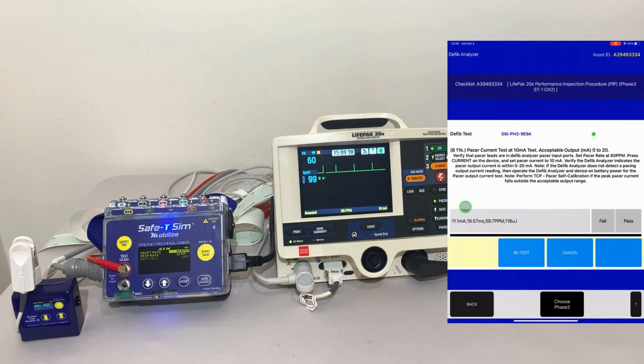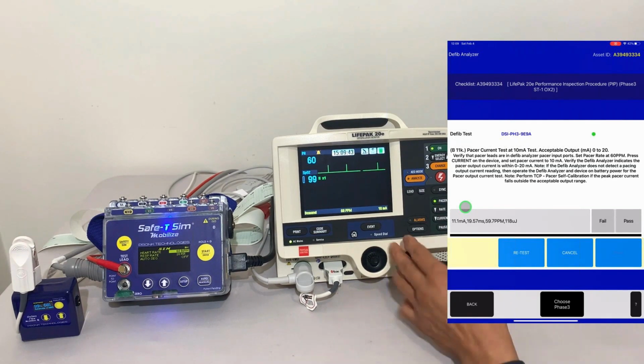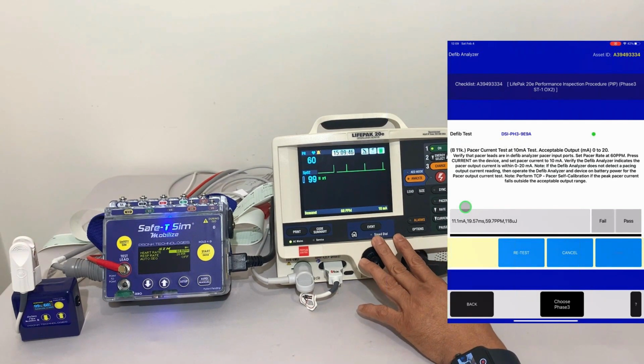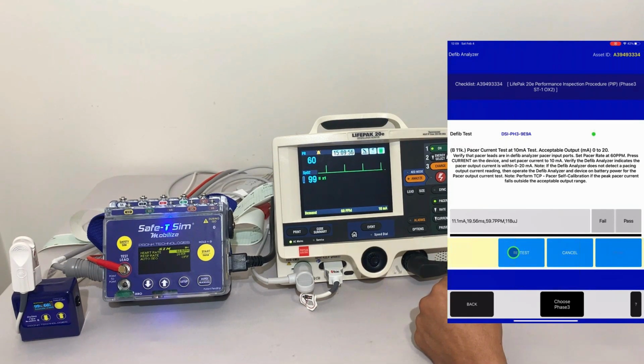If at any time you need to redo the test, maybe you have a measurement close to the edge of the tolerance, maybe you simply made an error and set the incorrect current on the defib, you can simply press the retest button. The analyzer will repeat the test, collect a new result, and confirm that result. So you can easily repeat the test without having to go back and repeat the entire procedure. We've passed this, go on to the next measurement.